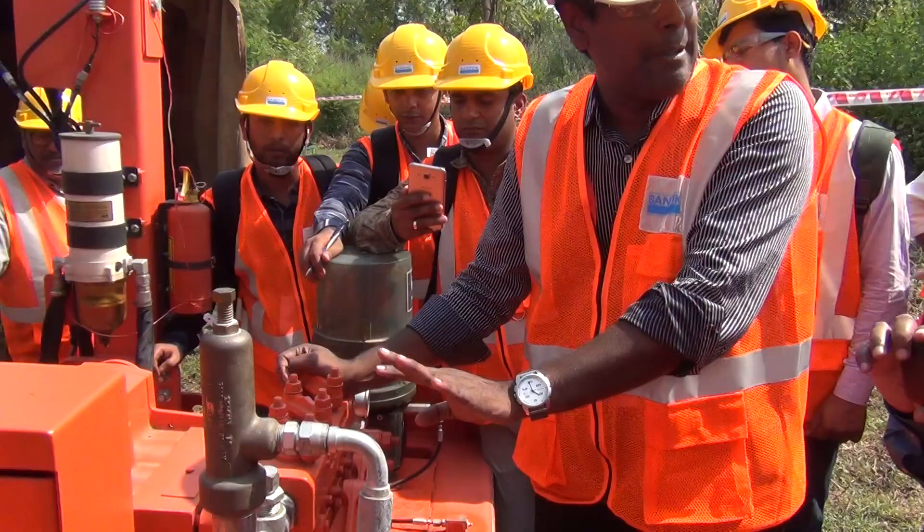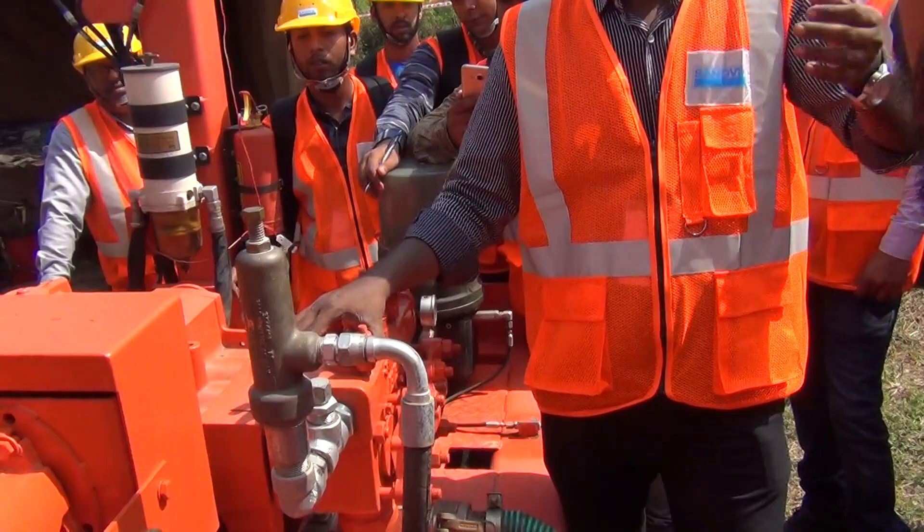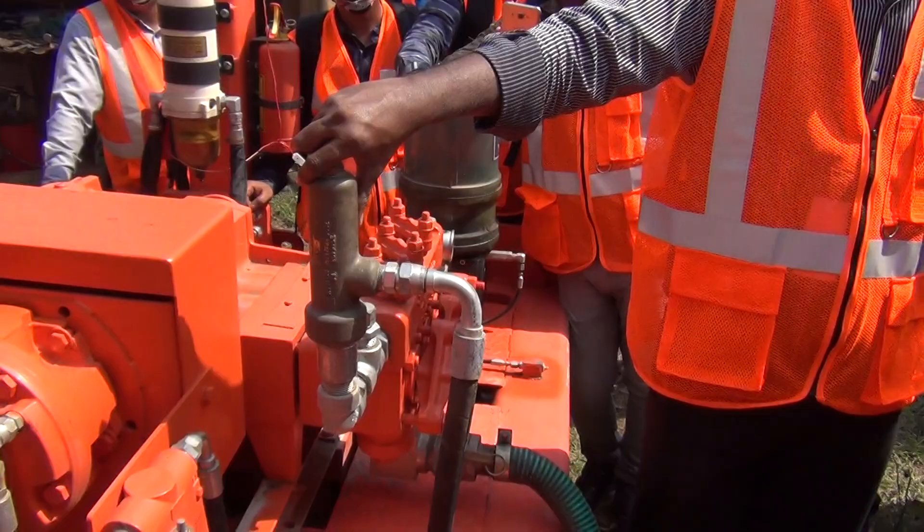This is normal check valve type — not plunger valve, not disc valve water pump. This is relief valve. Normally relief valve: 1000 PSI capacity. So maximum 600 PSI relief set. Water pump relief 600 PSI — we are setting.